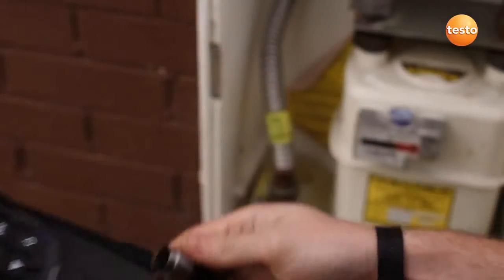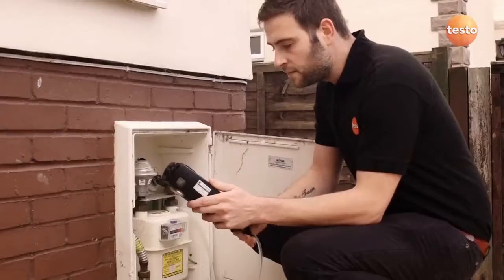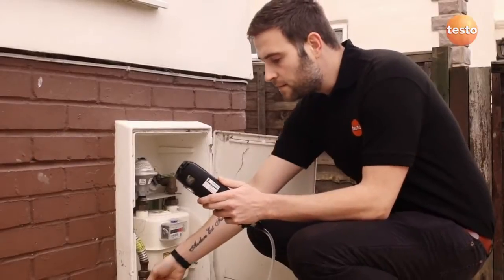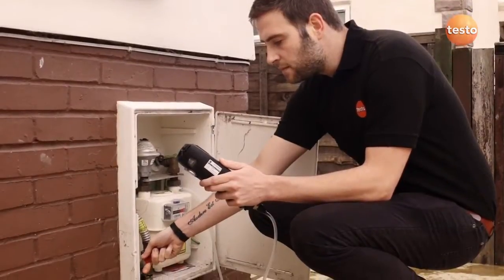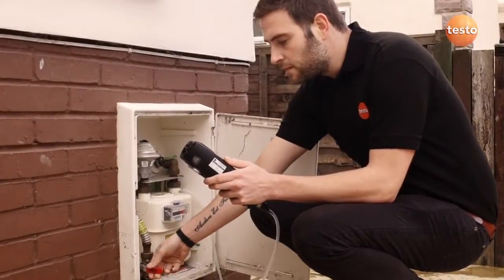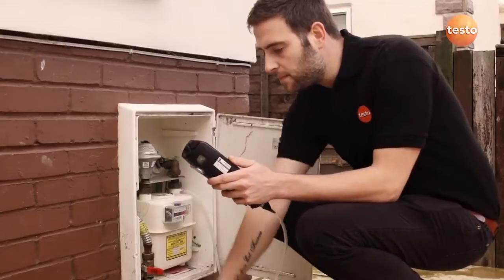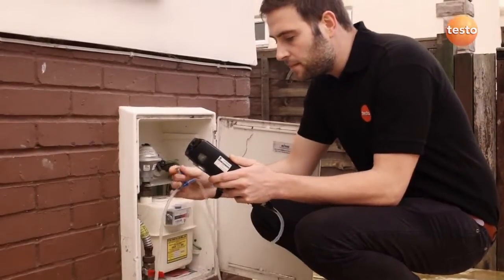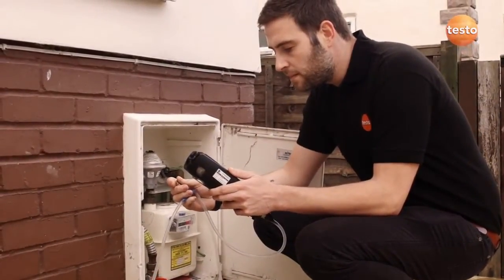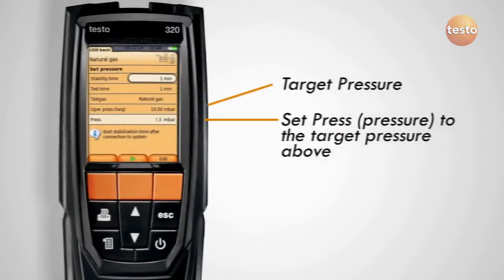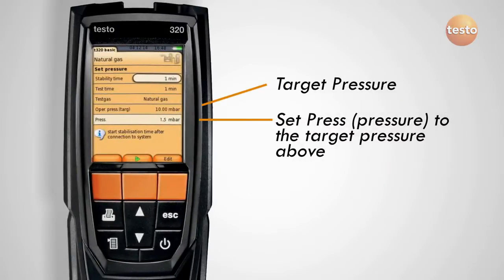Once the analyzer has zeroed, connect the hose to the test point on the gas meter and to the analyzer via the pressure adapter. Open the gas valve and pressurize the system and then close it again. Use the blue gas relief valve to reduce the pressure in the system to the target pressure shown on the analyzer. The pressure reading on the bottom line needs to be set to the target pressure shown above, in this case 10 millibars.